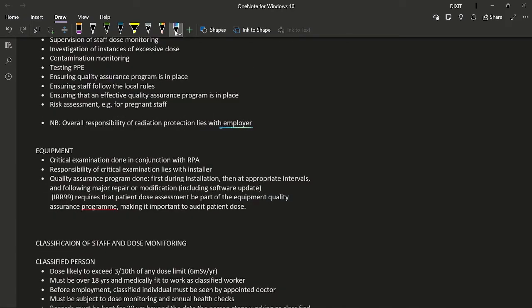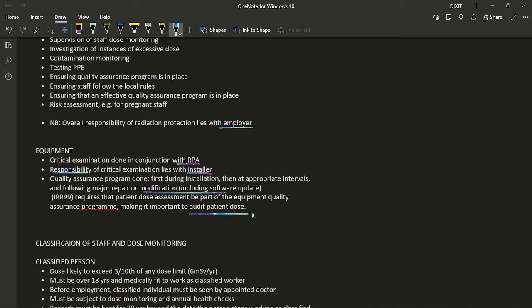According to IRR 99, the first critical examination of equipment must be done in conjunction with an RPA, but the responsibility for the critical examination lies with the installer. Quality assurance programs are performed during installation, at appropriate intervals, and following major repair or modification — even a software update counts as a modification. IRR 99 also requires that patient dose assessment be part of the equipment quality assurance program, making patient dose auditing important.